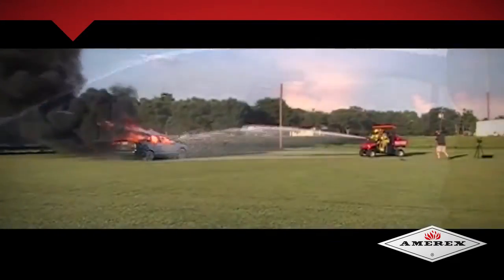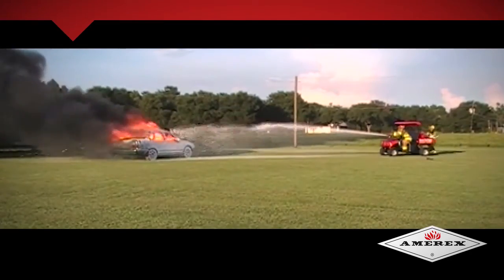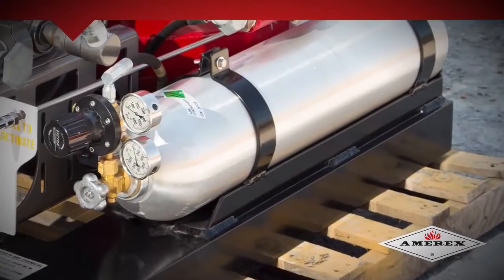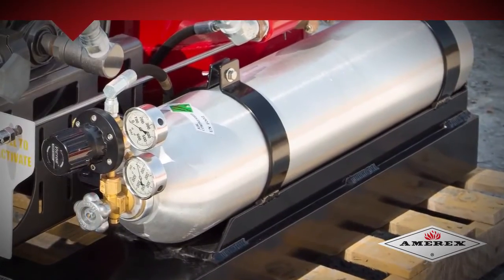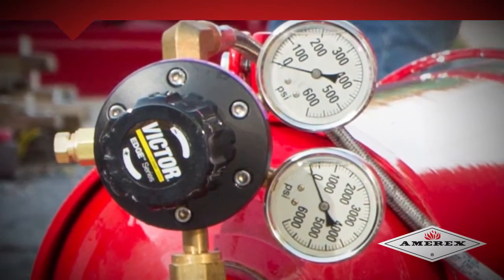By mixing the foam solution with compressed air during the expulsion process, Amerex CAV units are able to provide an extremely high expansion ratio foam from a very compact system. The viscosity of the expanding foam allows for a discharge range of 50 to 75 feet. Amerex CAV systems utilize compressed air or nitrogen tanks, making CAFs self-contained with no external resources required to operate the system.